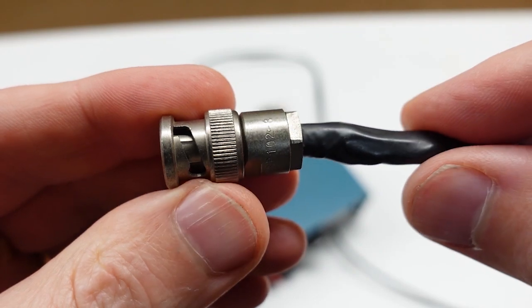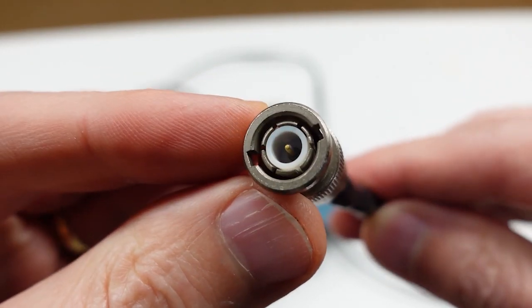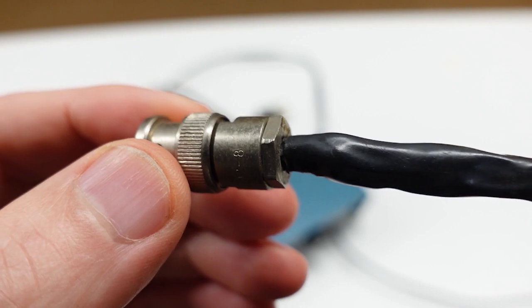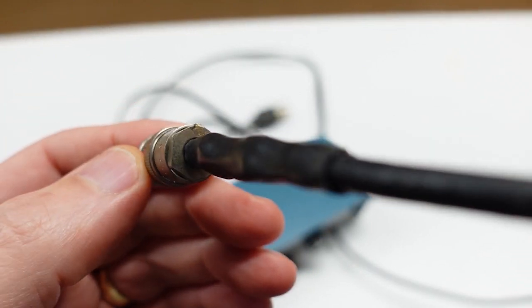It has two output signals. The first is a 200 millivolt square wave, and it's adjustable in 18 steps from a half second period to as fast as one microsecond. Or to convert that to frequency, that's from 2 hertz to 1 megahertz. Specified frequency accuracy is a decent plus or minus 0.01%, with an equally decent maximum rise time of 4 nanoseconds. This signal is provided on a short length of coax terminated in a male BNC connector with an internal 50 ohm load.